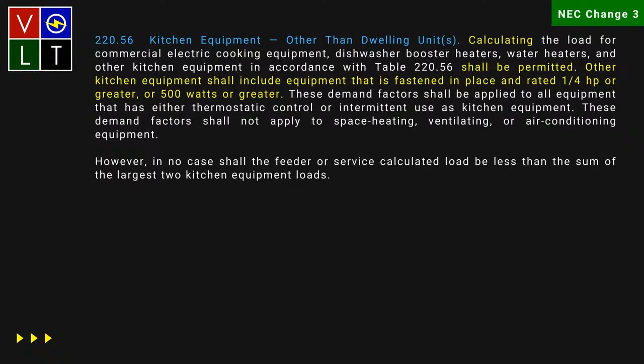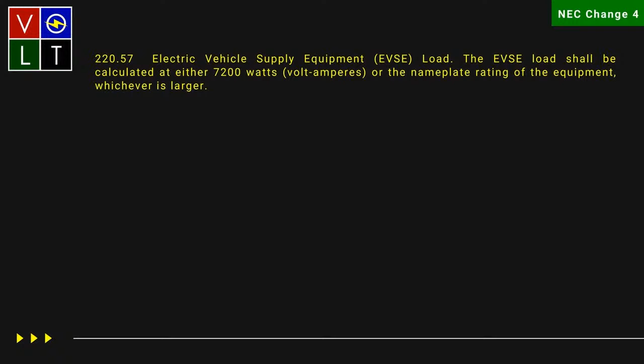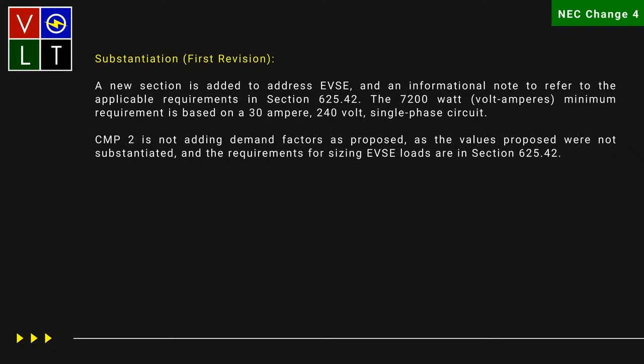Yeah, that makes sense. And then right here, you'll see where they added 220.57. I couldn't remember the wattage today, but when you're dealing with electric vehicle supply equipment, it tells you that the load has to be at least calculated at 7,200 watts or volt-amps, or the nameplate rating of the equipment. So you'll have to do 2 calculations here to determine which one is larger, and based on that, that's what your amperage will be. But based on Article 625, these loads have to be taken at what? 125% on that nameplate. So that was a change that was there. And this gives you an example here, with 7,200 being the minimum requirement, and that is based on a 30 amp, 240 volt single phase circuit.